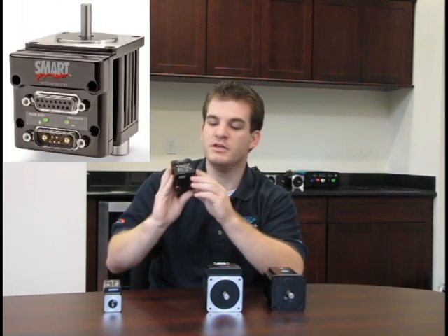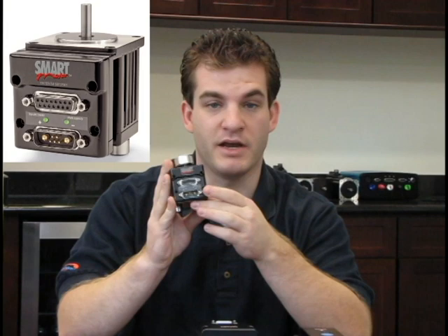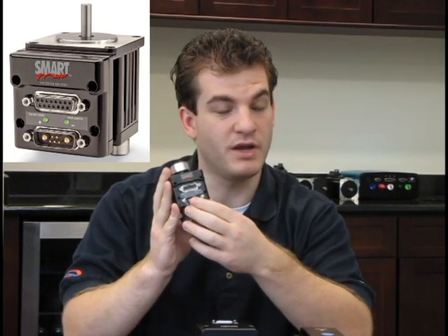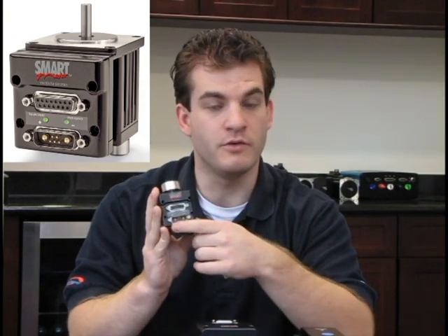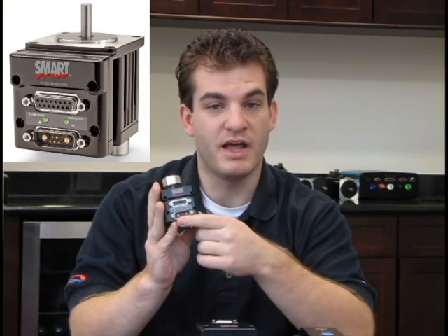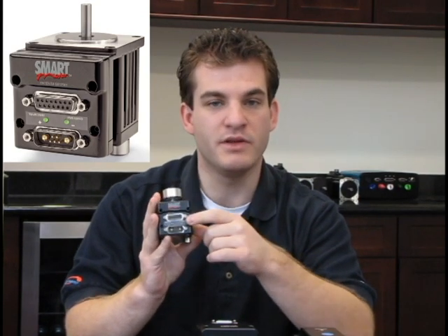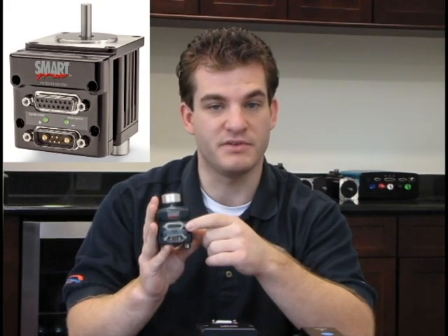Let's take a closer look at a smart motor. The bottom D-sub connector is a 7W2 hybrid connector. The two largest pins are for drive power, 24 to 48 volt DC. The smaller pins in the center are for your RS-232 serial communications, as well as a 5 volt trigger. The LEDs in between them indicate power or trajectory, or if the motor is maintaining a position.